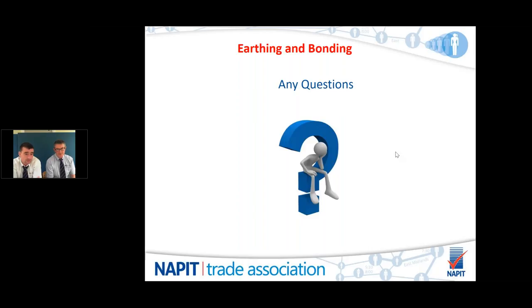Just going on from what you said with the wandering earth lead test, what you'd be looking for as a value is below 0.05 for your reading, and that'll tell you you've got an adequate earth. But again, if you was doing an EICR and you was questioning the size of the bonding, if you've got a 6 mil there, is it immediately dangerous or does it just not comply? So you'd C3 it. There's a lot of things to take into consideration, really.